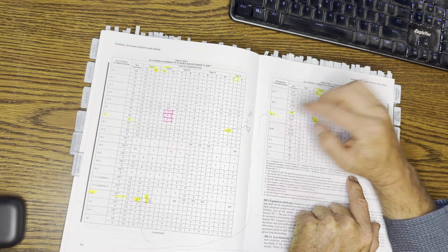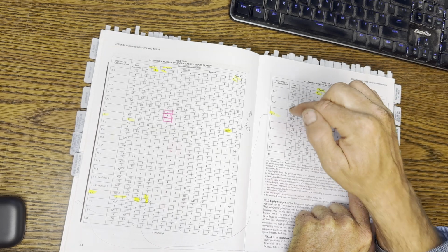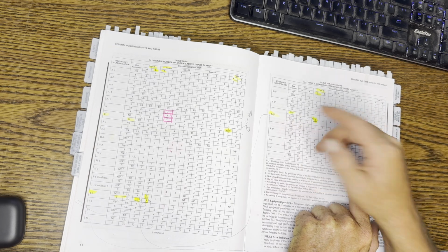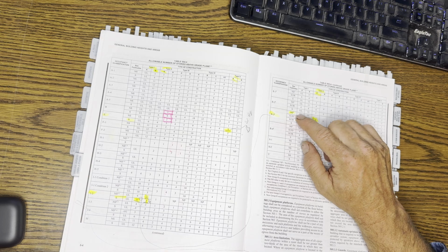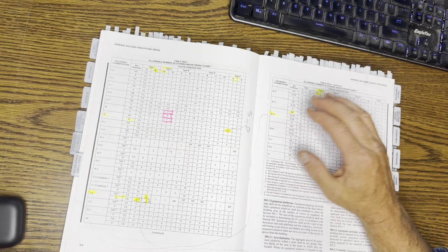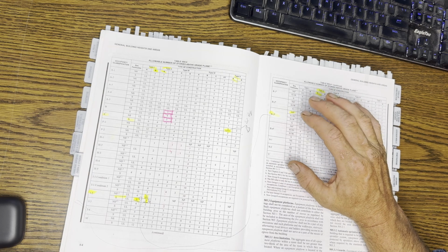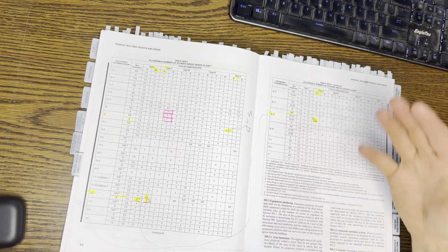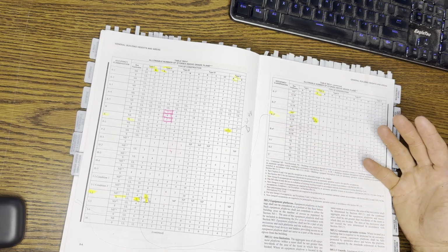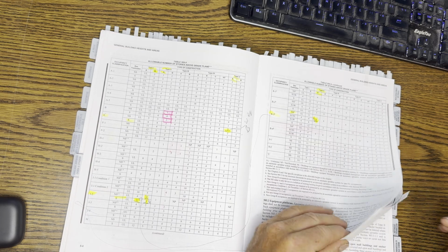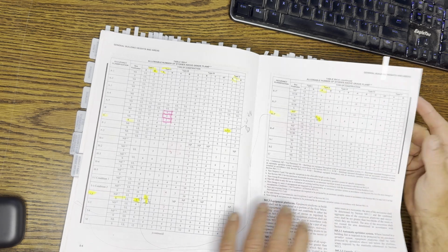Well, if R's, and you go to section 903, I'll show this to you, R's always require suppression. Well, why do you allow no suppression? That's because most municipalities modify this. Most municipalities, domestically in the United States, when they adopt the ICC code set, say apply this code except that R3s don't need suppression. So that's why you have the option. It's very common. I could tell you some stories why it's in the code. It's kind of ridiculous. It's corporate money at work.